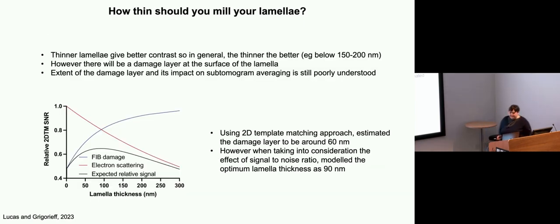The other question one needs to consider is how thin to mill the lamella. Generally, the thinner you go, your tomograms look much better. So ideally you want to go below 200 nanometers. However, there is this question of damage during the milling process and that there'll be damage at the surface. Now, depending who you ask, this can range anywhere in the sort of 30 nanometer damage layer. That was done from using simulations of stopping distance, simulations of the gallium ions interacting.